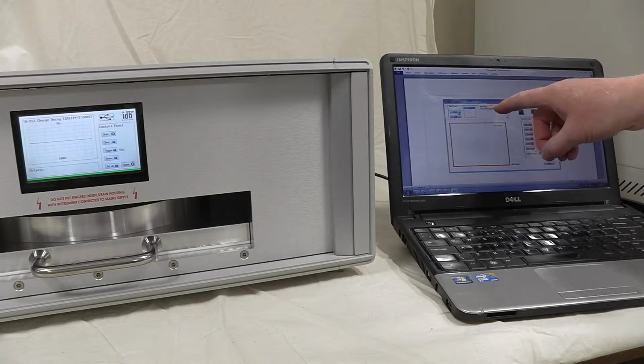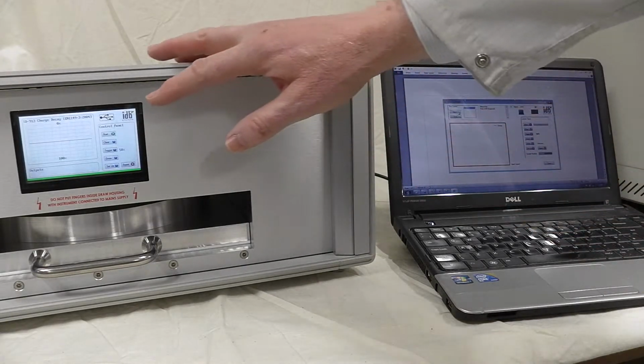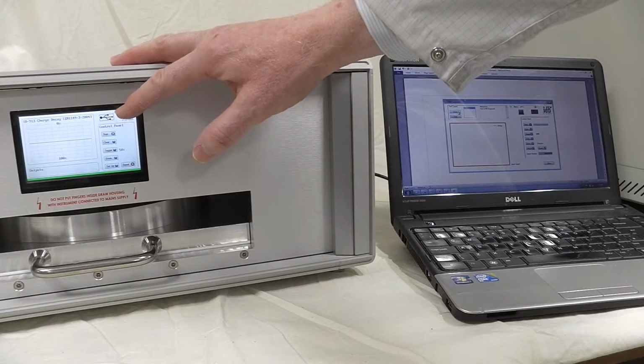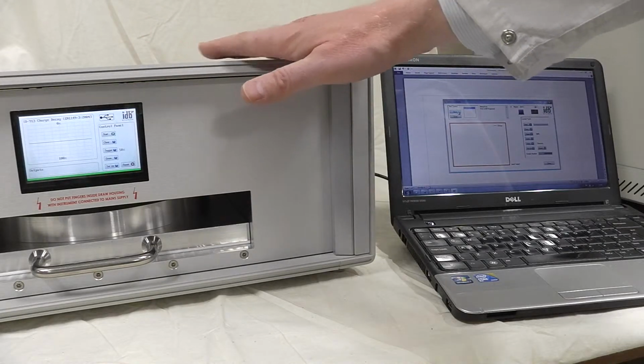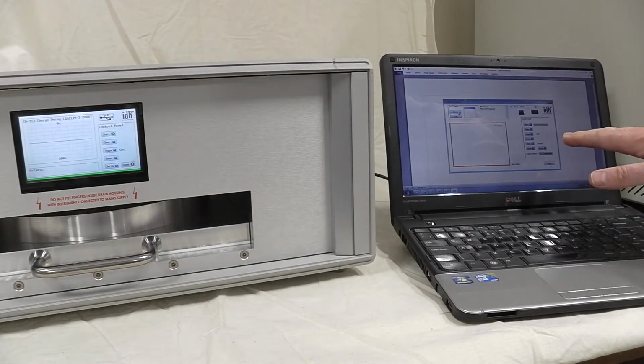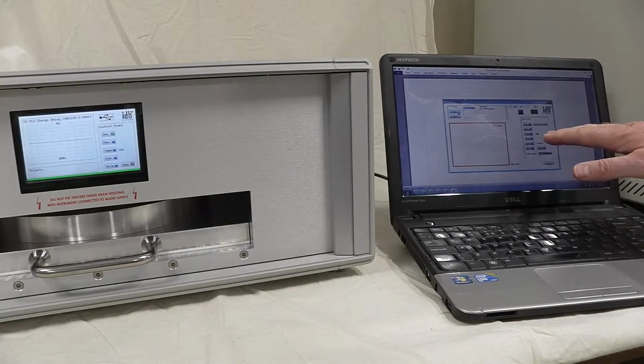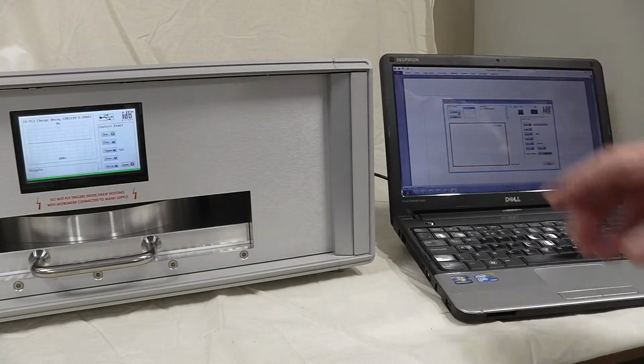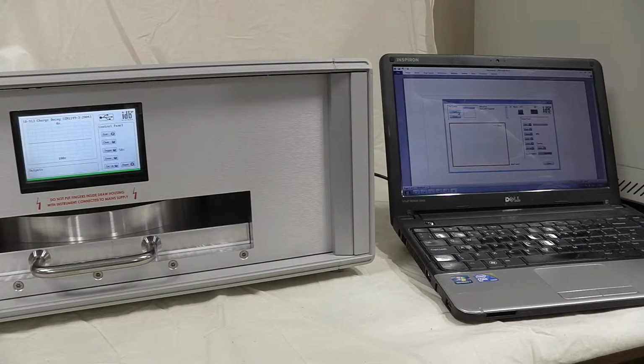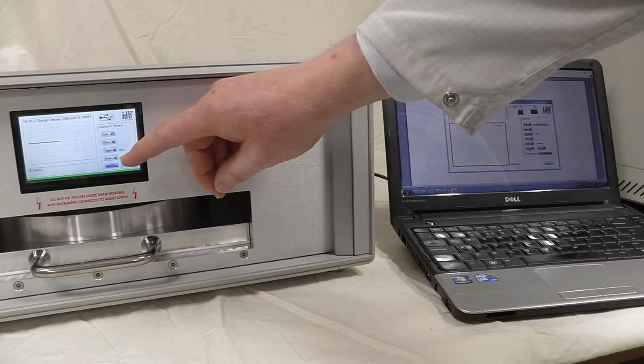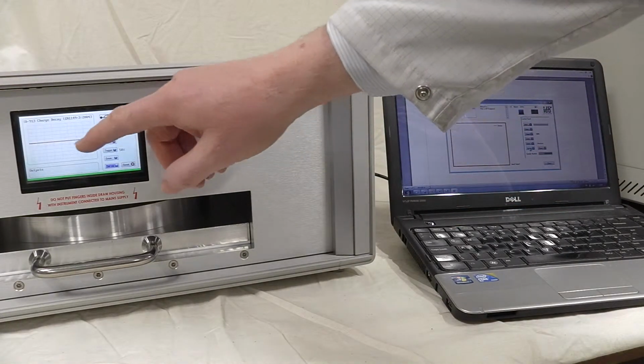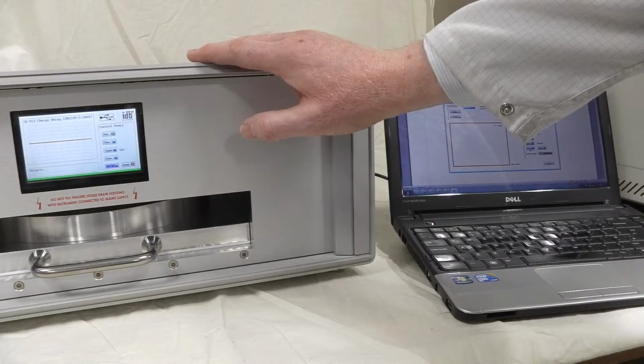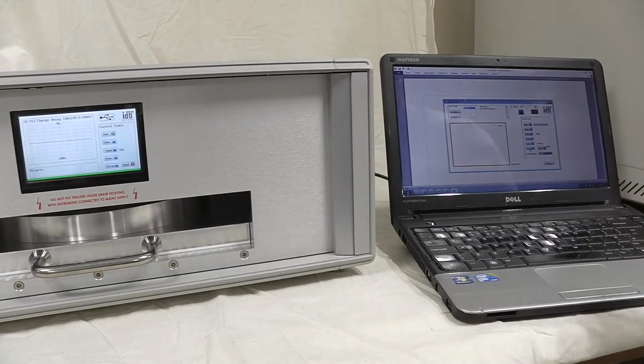instrument, and we have a little memo pad here that shows us port COM15 has been opened, and if you observe on the instrument we've got a little USB logo that says the instrument recognised that the PC is connected to it. From there on, it's pretty much exactly the same way of controlling the instrument.